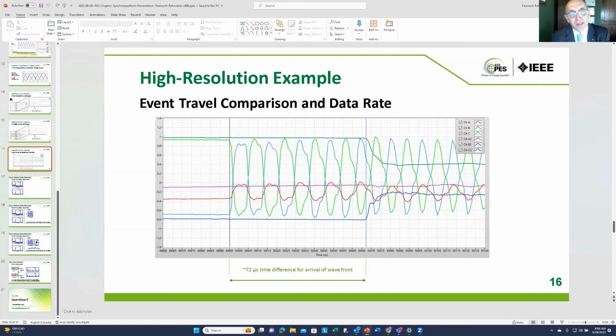But what about the amount of data that you receive? This needs a clusterization of the information. Correct, correct. So we apply this with the project, with the people we work with. These particular sensors, for example, do have synchrophasor output, which is like any other PMU streaming out, people can use it or not. There is sampled value output, which again, like any merging unit, people can hook up to a relay, not too far, usually within the substation.